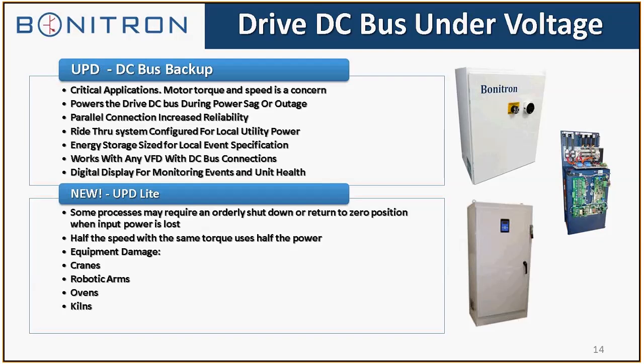Now, we also have come up with a new method of providing ride-through, which is called UPD Lite, and it is partial power ride-through. Some customers only want to be able to ride through long enough to bring the process back to zero position. So, in other words, you don't need full ride-through power. You can provide enough ride-through power to the DC bus to just hold up the drive until it jogs back to zero position.